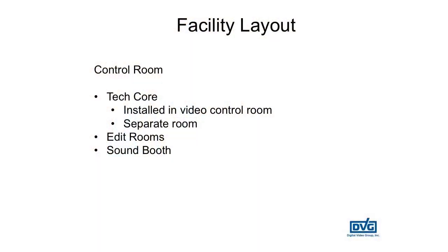Then we move to the tech core. Is it going to have a separate room, or are they just planning on putting the racks inside the control room? Well, if the control room is 8 by 10 and you got to put 2 racks in there plus an operating console, it gets awful crowded, awful hot, and awful loud. We've gone back and forth in many facilities where they want us to move the racks after the fact, a year or two later, out of the control room into its own dedicated room. That's a major project, especially if you don't take that into consideration right up front, because the cables you installed 2 years previously aren't long enough to accommodate moving to a different room.